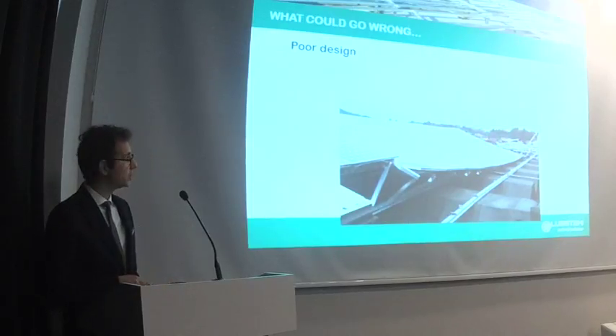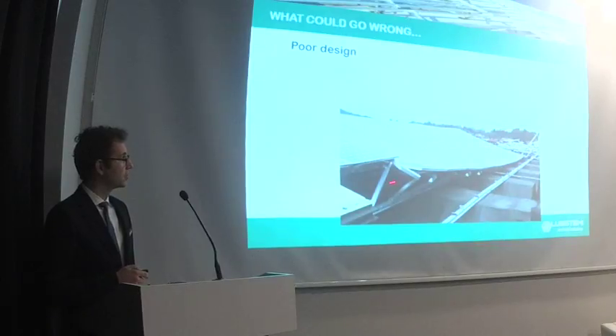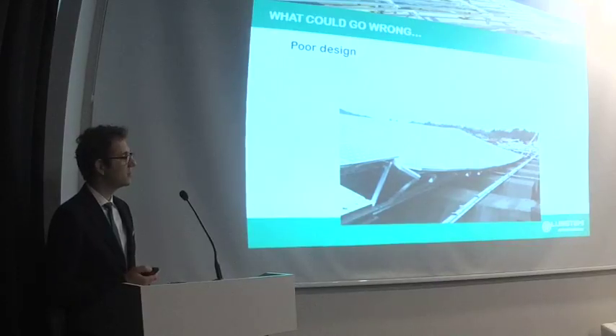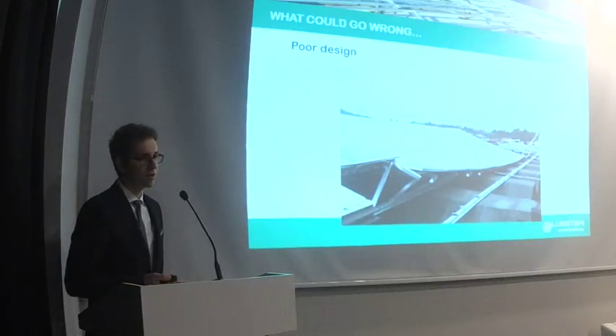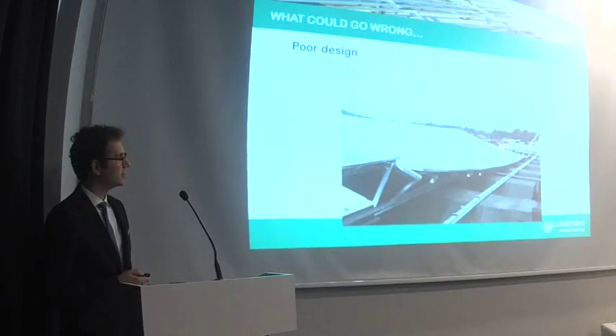First of all the structures broke the roof windows, and then about a third of the modules burned out, and part of the structures went down onto the street near this factory. The problems could have been avoided by using 50 euros of aluminium to brace behind the structures. In this case, the cost of the repair is far higher.